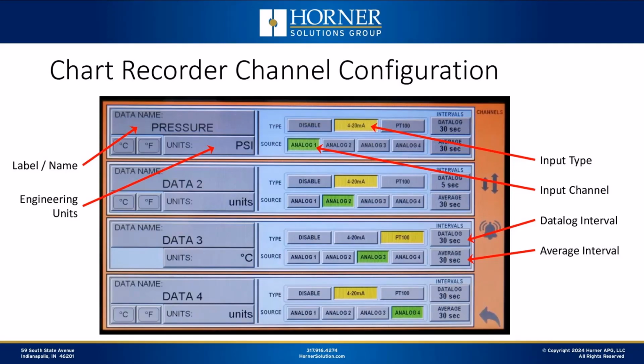So let's take a look at what the channel configuration looks like on the unit. Along the left-hand side there, you can type in a custom name or label for each of your 4 analog inputs. In this case, we've got pressure as the top one on the upper left. You can also type in the engineering units, whether it's PSI or bars or whatever the particular analog value has in terms of engineering units, so that you're looking at everything where it makes sense from an engineering unit standpoint.